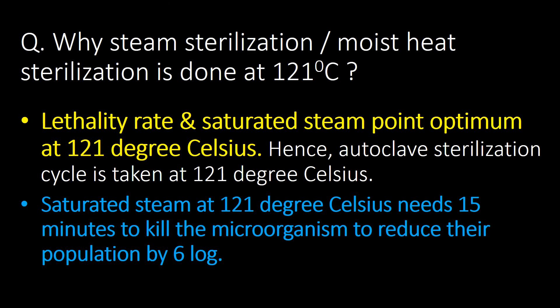While steam sterilization or moist heat sterilization is done at 121 degrees Celsius, the lethality rate and saturated steam point are optimum at 121 degrees Celsius, hence the autoclave sterilization cycle is taken at 121 degrees Celsius. Saturated steam at 121 degrees Celsius needs 15 minutes to kill microorganisms and reduce their population by 6 log.